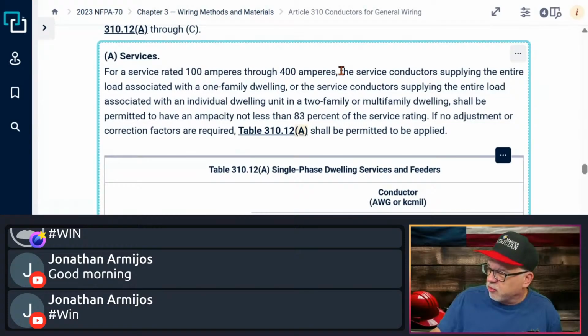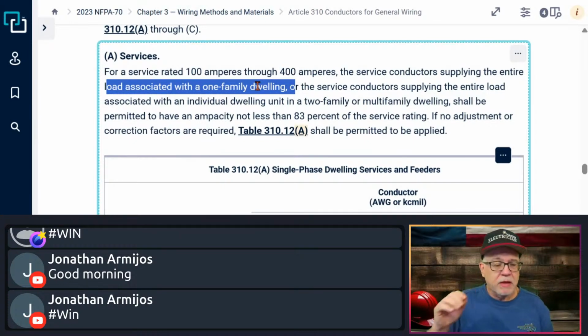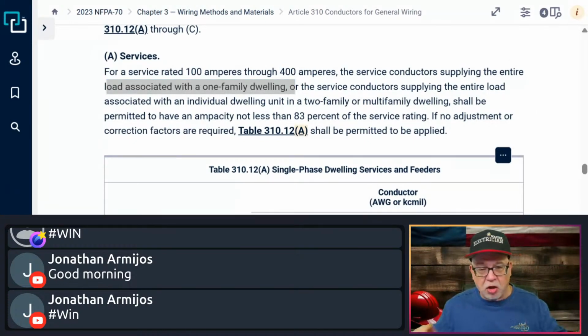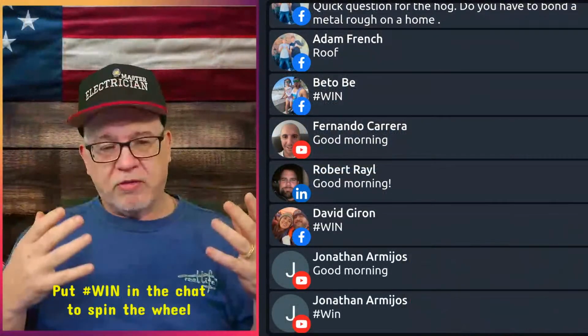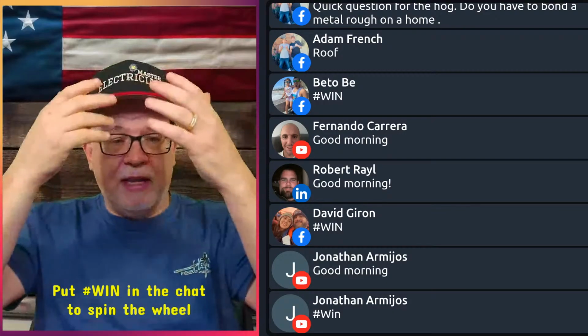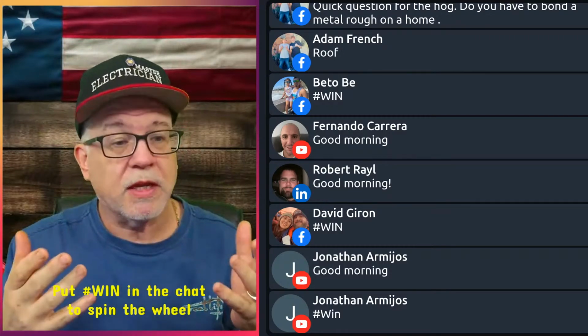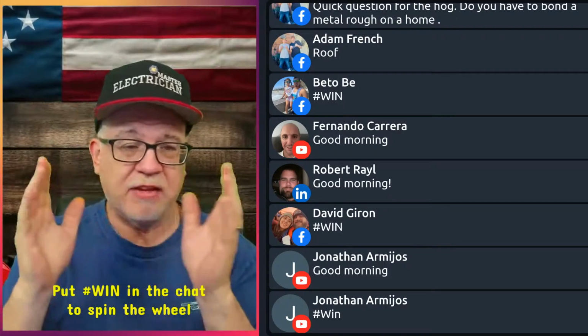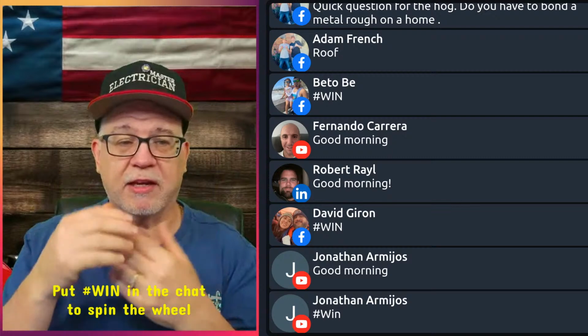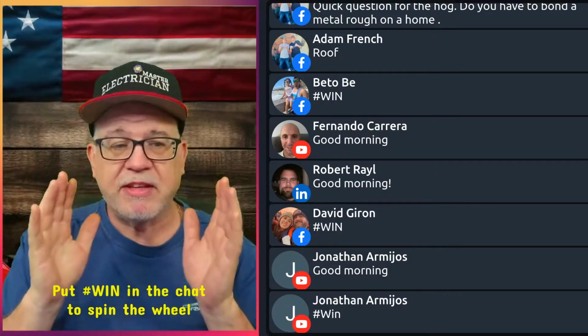And so it says the service conductor supplying the entire load associated with the one family dwelling. So y'all have heard me talk about that. So just to give you the visual of when it says the entire load and when you can do this, mental picture time. So if I was coming from a weatherhead and my SE cable, all that is running down the side of the house or side of the building and it's going into the meter, okay? And then it's coming out of the meter and it's hitting a panel on the outside. Say it's a main breaker, it meets the requirements, exterior emergency disconnect, it meets the requirements. It's the overcurrent protection, it's the overload protection, 230.90. Everything's fine. It meets 230.85 exterior emergency disconnect.